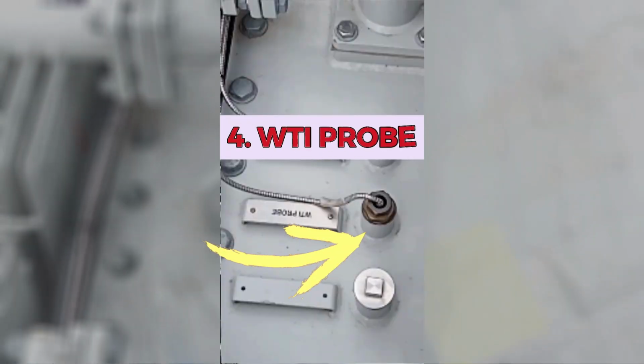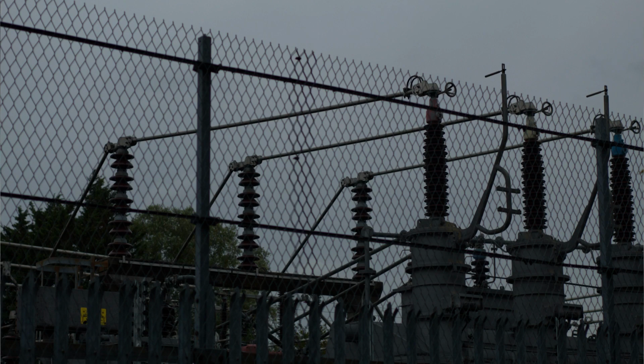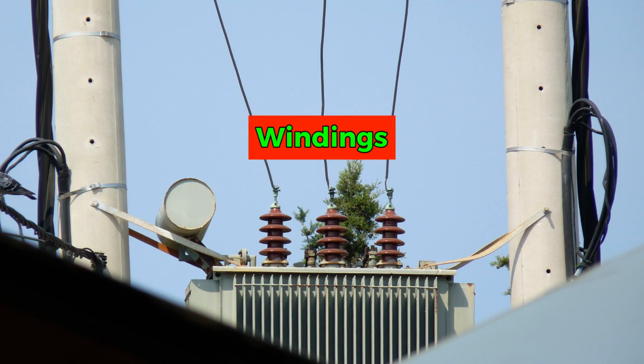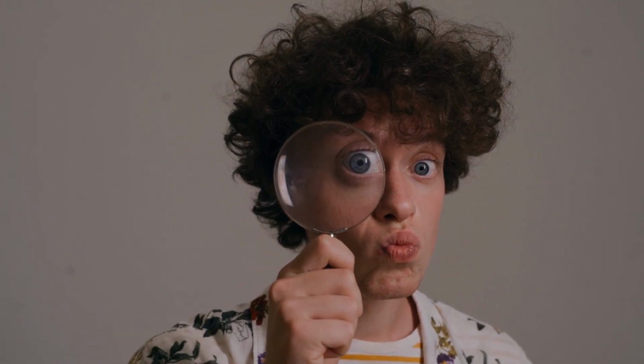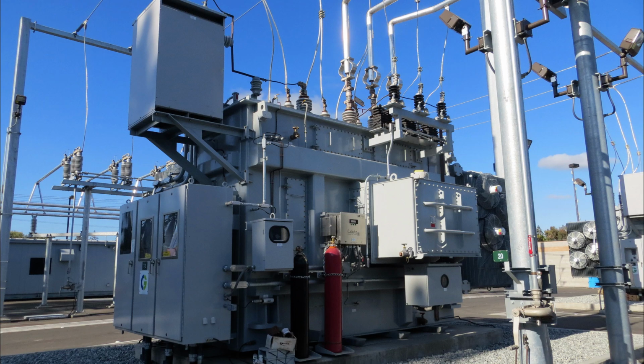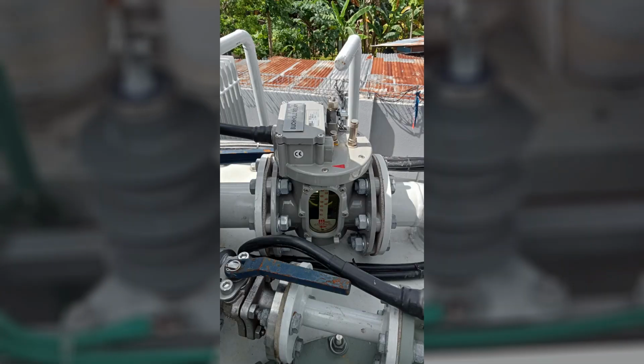Now, let's talk about the WTI probe, or winding temperature indicator. This device is responsible for monitoring the temperature of the transformer's windings. By keeping an eye on the winding temperature, we can ensure the transformer is operating within safe limits.